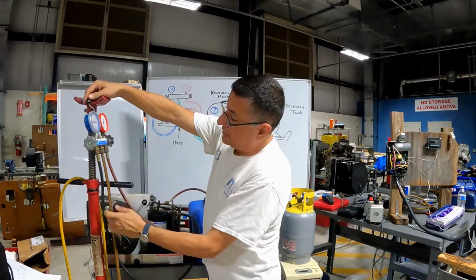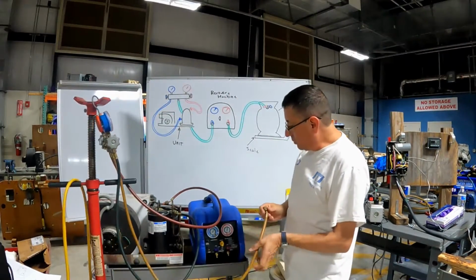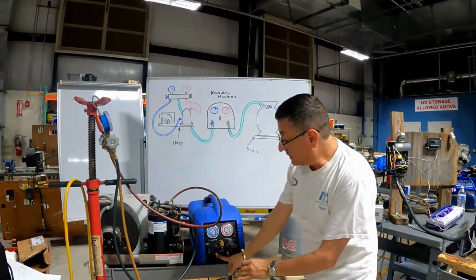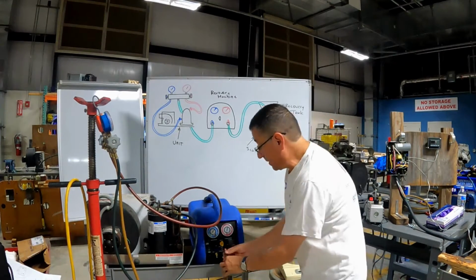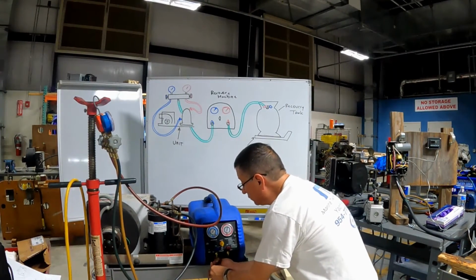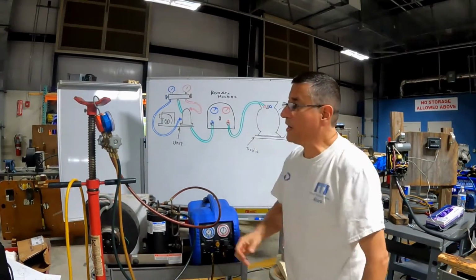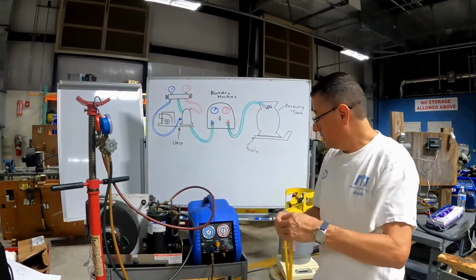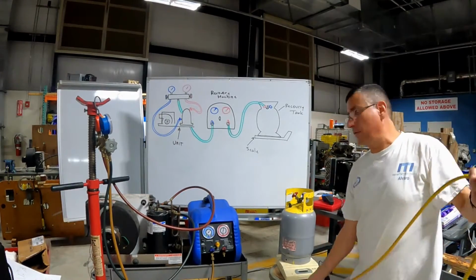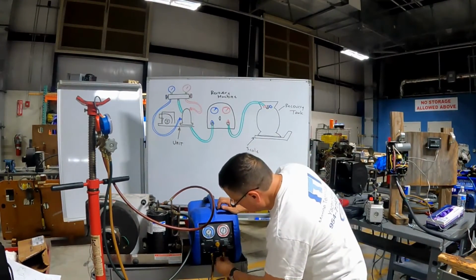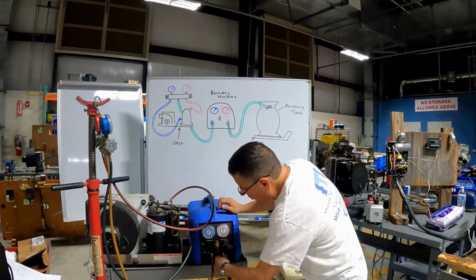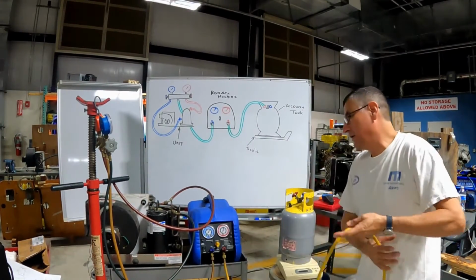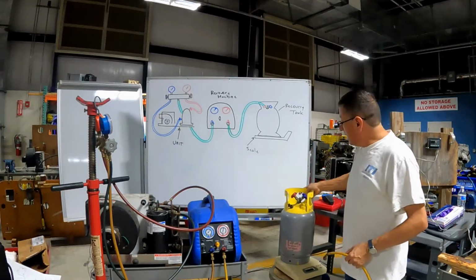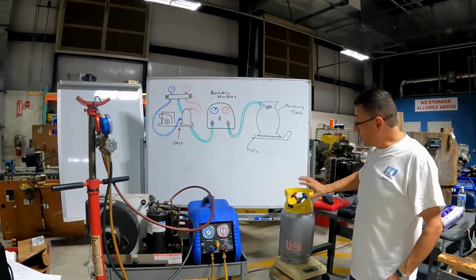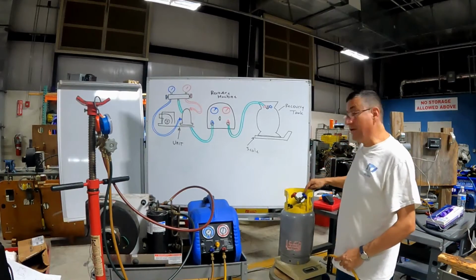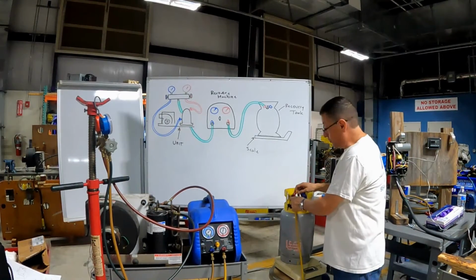the middle one, the yellow one, will be connected with the suction side of the recovery equipment. We're going to connect this one here in the suction side, and we are going to connect the extra hose from the discharge side of the unit into the liquid port of the cylinder. You have liquid and you have a vapor. In the liquid port or high pressure port.